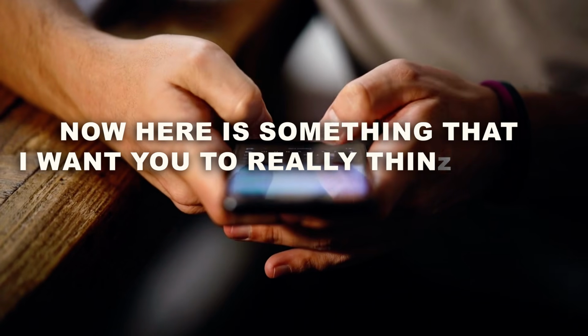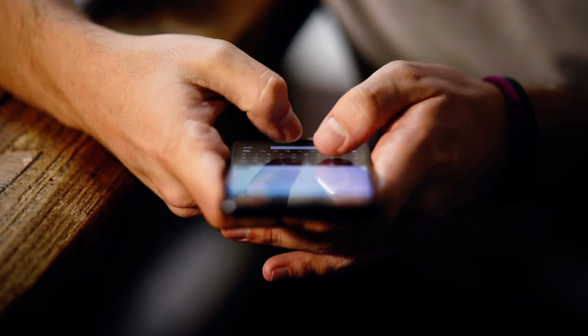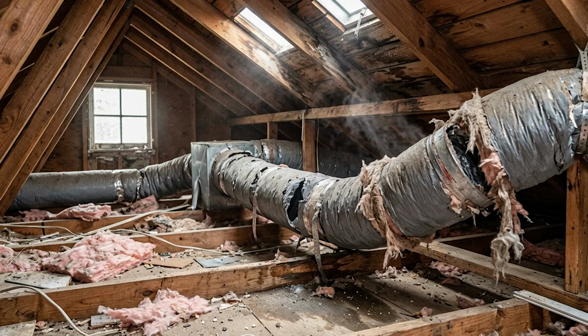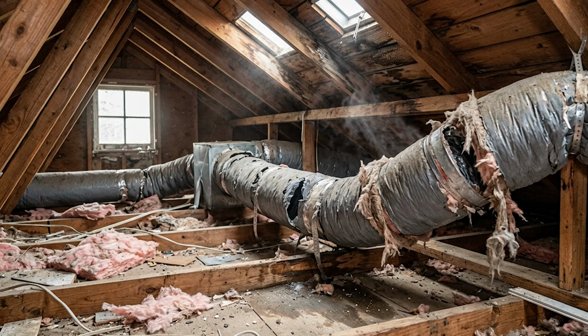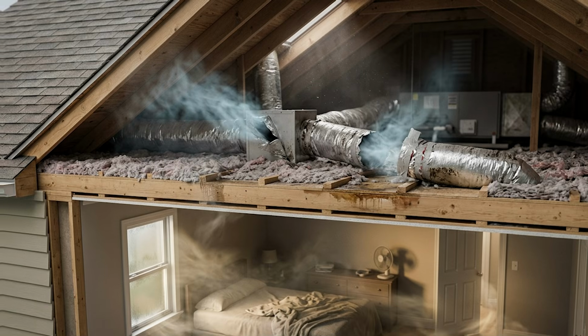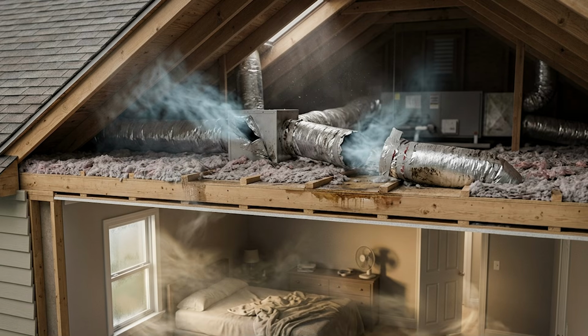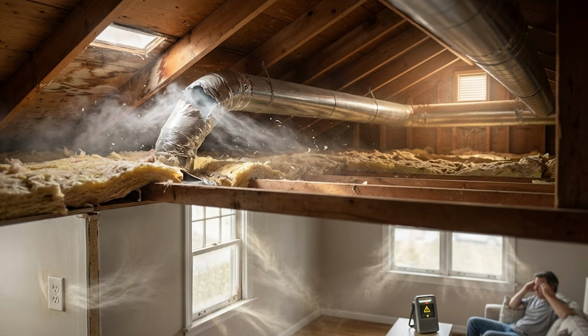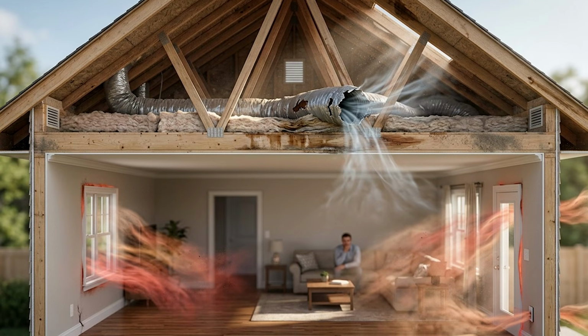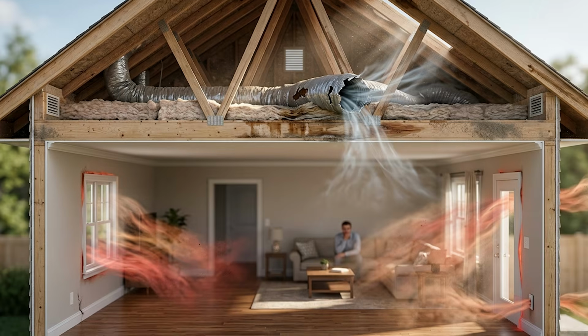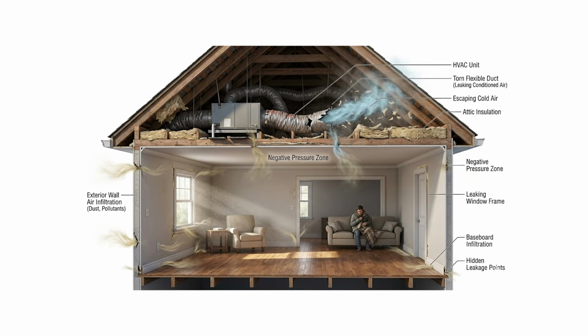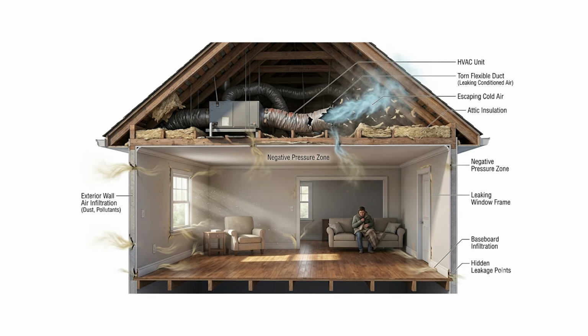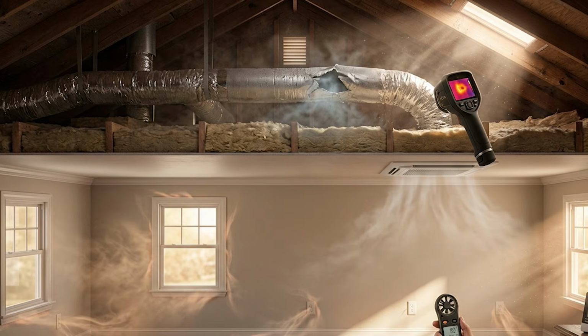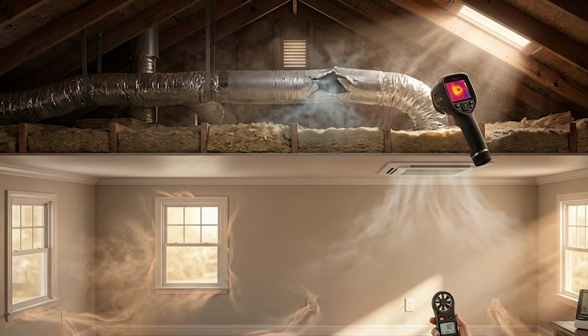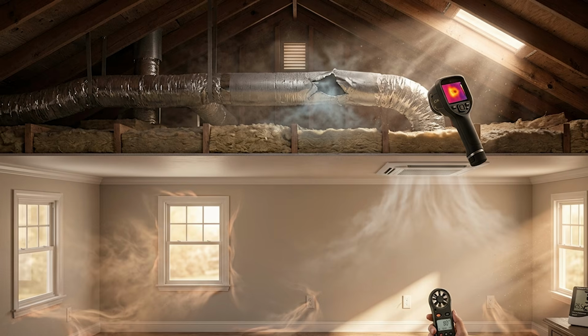Now here is something that I want you to really think about, because this one genuinely surprised me. When a supply duct leaks in your attic, it is not just losing the conditioned air that escapes. That escaping air creates a drop in pressure in the room it was supposed to serve, and nature does not allow a pressure difference to just sit there. So the room pulls in replacement air from wherever it can find it, from gaps around window frames, from spaces behind electrical outlets on exterior walls, from cracks where the baseboard meets the floor. Outside air, hot, humid summer air, being pulled directly into the room that your air conditioner cannot seem to cool.